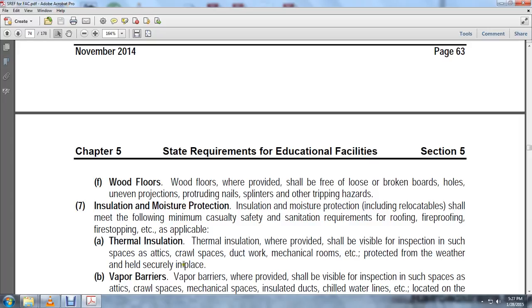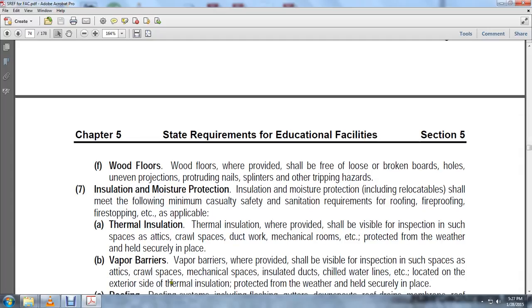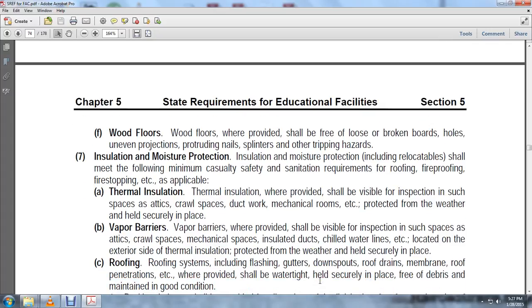Vapor barriers, where provided, shall be visible for inspection in such spaces as attics, crawl spaces, mechanical spaces, insulated ducts, chilled water lines, etc., located on the exterior side of the thermal insulation, protected from the weather and held securely in place. Roofing systems, including flashing, gutters, downspouts, roof drains, membrane, roof penetrations, etc., where provided, shall be watertight, held securely in place, free of debris, and maintained in good condition.